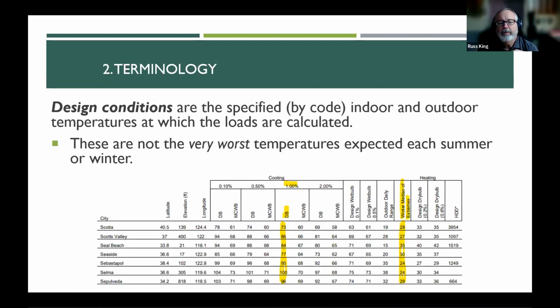Now, when we do a load calc, we do it at certain design conditions, okay? So when I say your air conditioner has to work on a hot day and your heater has to work on a cold day, well, what's a hot day and what's a cold day? Those are statistically derived numbers that are specified by code. Code requires that you pick a certain temperature based on the city that you're in, okay? So here's an example of the table that we use. Design conditions are specified by code for indoor and outdoor temperatures at which the loads are calculated. These are not the very worst temperatures expected each summer and winter. You might say, gosh, we just hit 100.